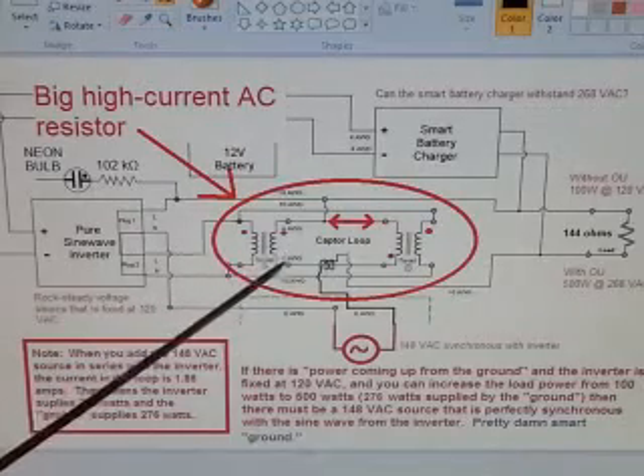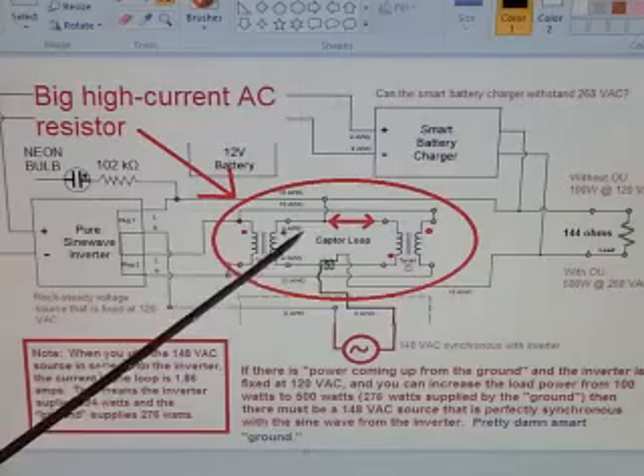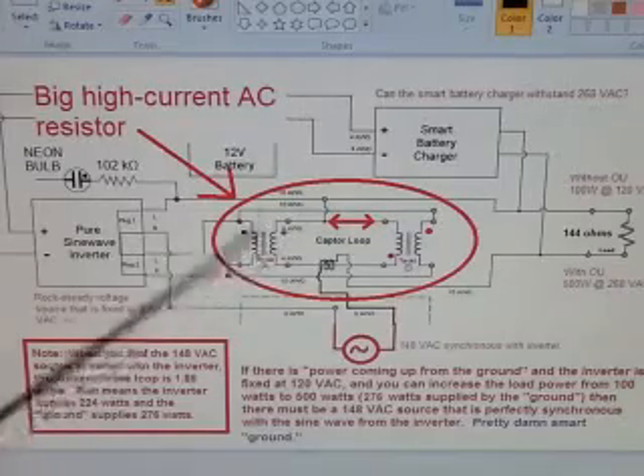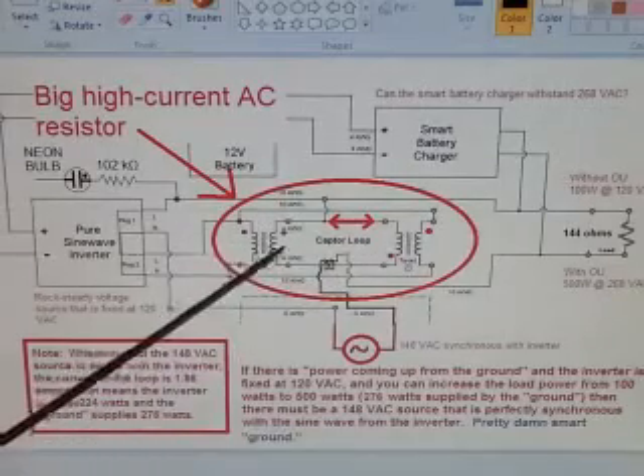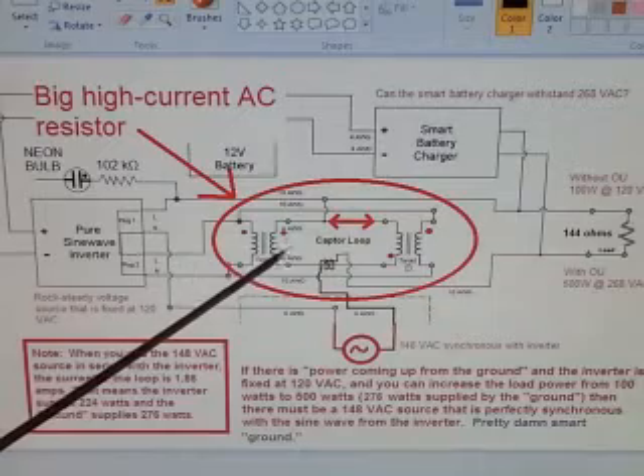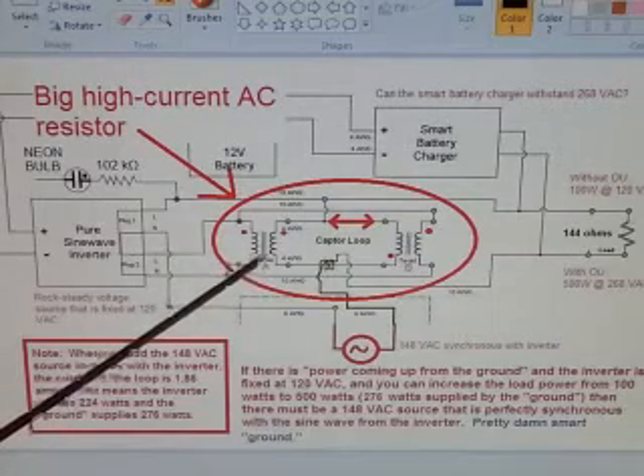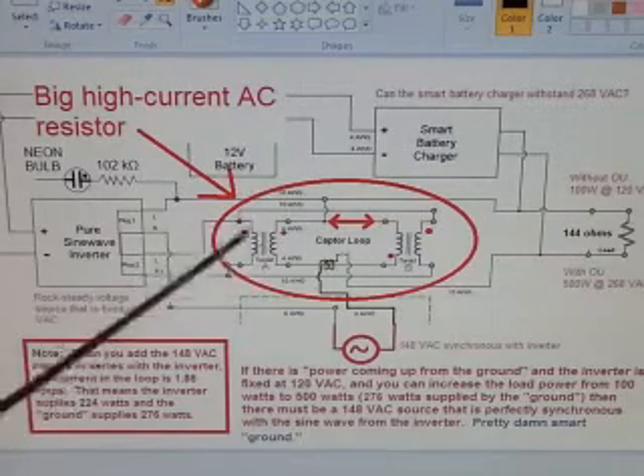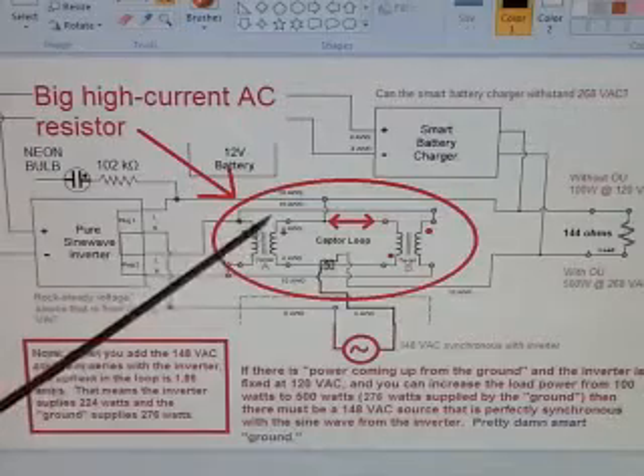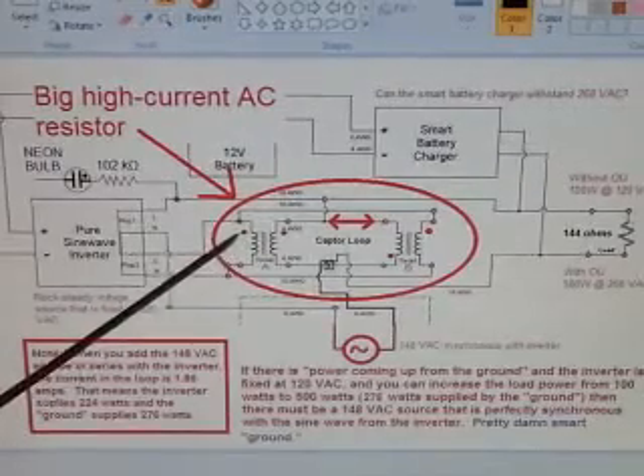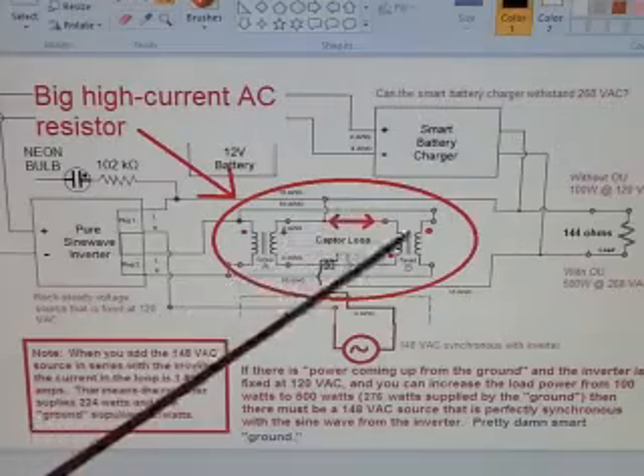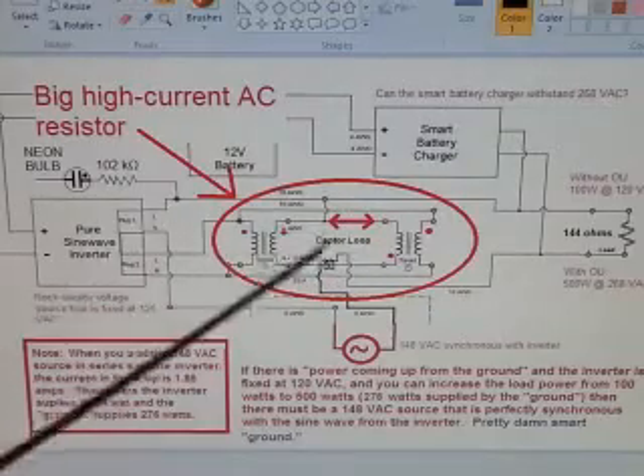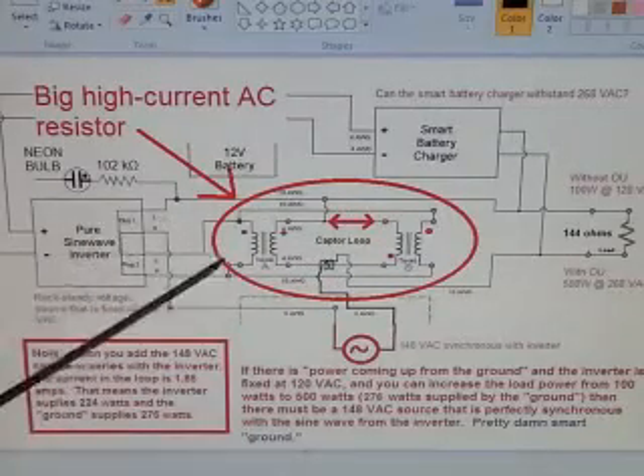Usually it's 2.5 turns of this 4-gauge wire. But when you have only one transformer and you lose this one, you only go around once — or really it's a half turn, because it doesn't even go around, it just goes through the interior of the transformer. Then the excess is coiled around the transformer rather than going through the interior.